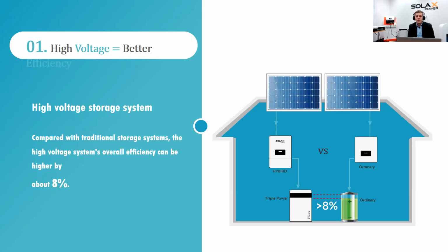Compared to older systems with a separate PV inverter and battery inverter, you have less energy loss because the DC power is stored in the battery directly. There's no conversion between storing—the only conversion happens when it puts power out to AC, which is the usual conversion loss you'd have in any PV grid system anyway. So there's only one conversion loss, going to AC.